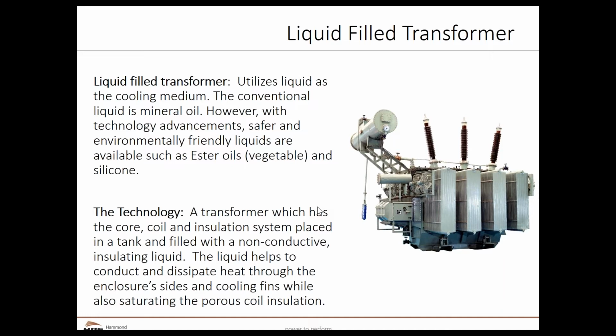The big difference, though, is that with a liquid filled transformer, they take the core and coil and put it into a tank. Basically, it's called for what it is, a fuel tank, and they then submerge that transformer in a liquid. Typically, people have referred to it as oil, and the oils range from something that would be termed diesel fuel, to more modern mineral oils, and even more modern designs would use what we call ester oils, which are a vegetable-based oil, or some type of liquid silicon technology. And again, the entire transformer is submerged in this liquid. The liquid is obviously non-conductive, and the heat that the transformer generates is transferred to the liquid, which is then transferred to the tank walls and or cooling fins.